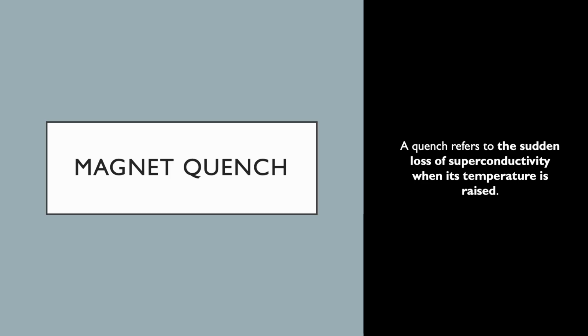Next up, we are going to look at what happens following an MRI accident, which in most cases is a quench. So let's define a quench. A quench is when helium is quickly released from the MRI machine. This causes the machine to be non-superconductive and eliminating the magnetic field. Simply put, the machine is not a running magnet anymore.